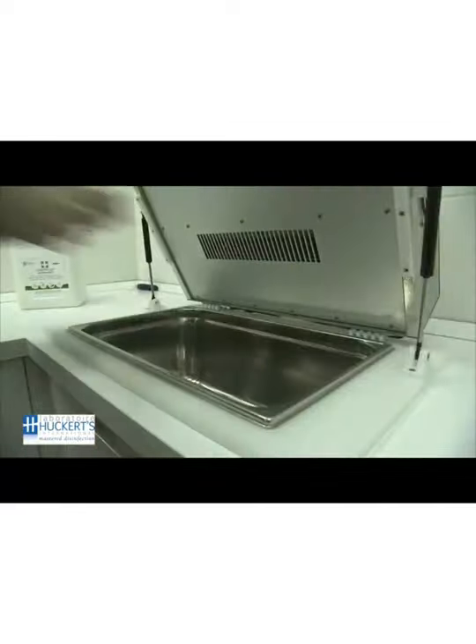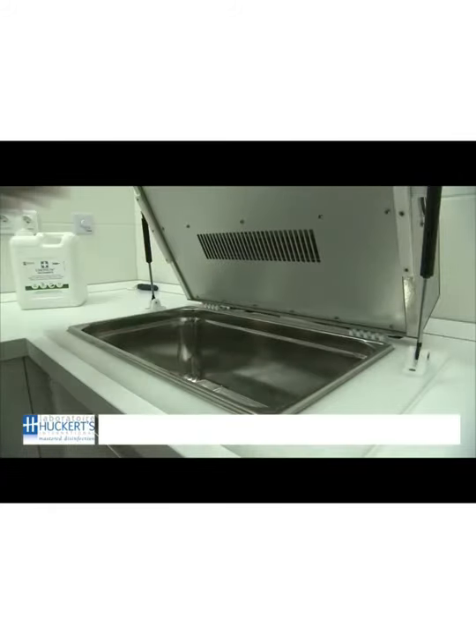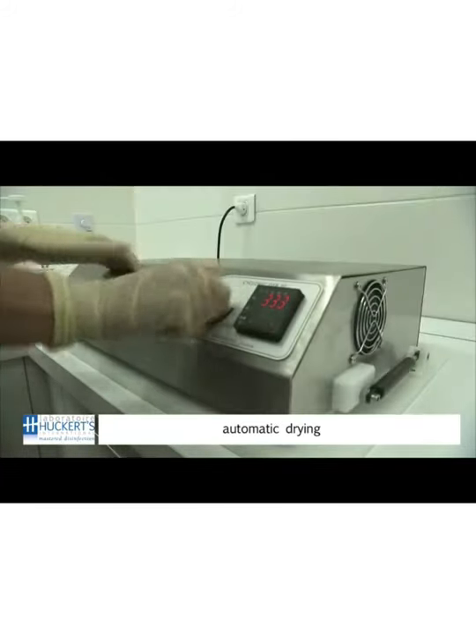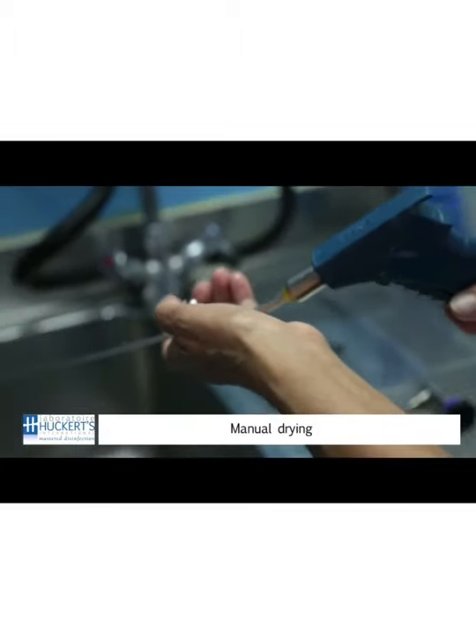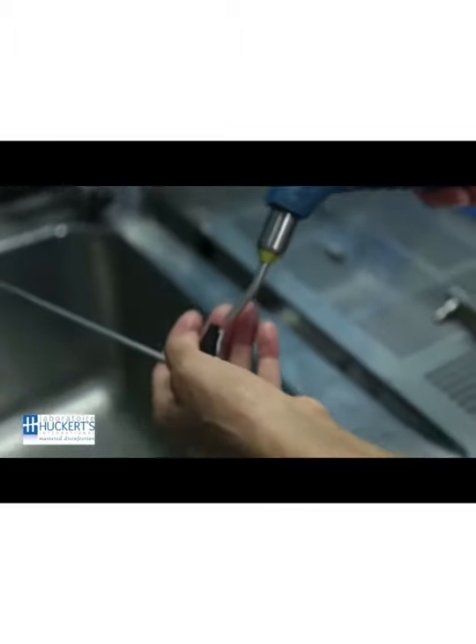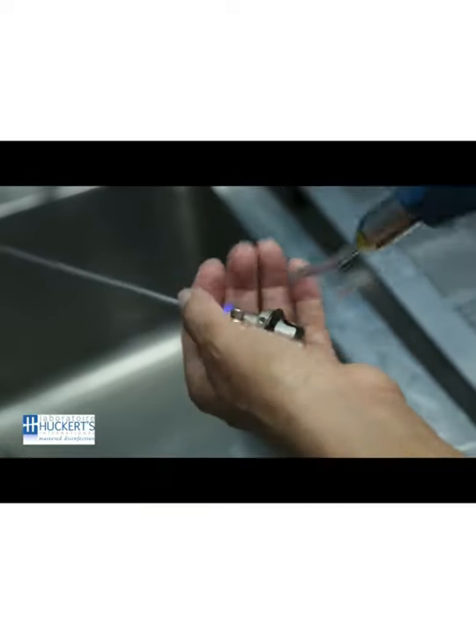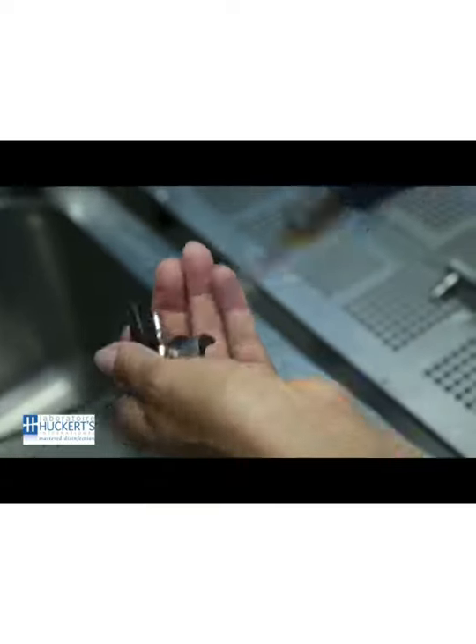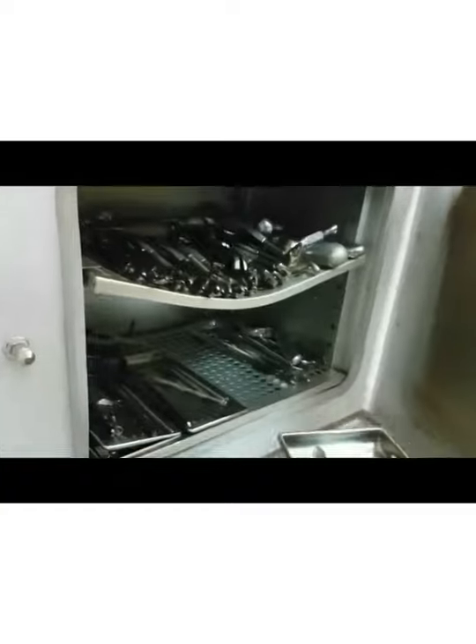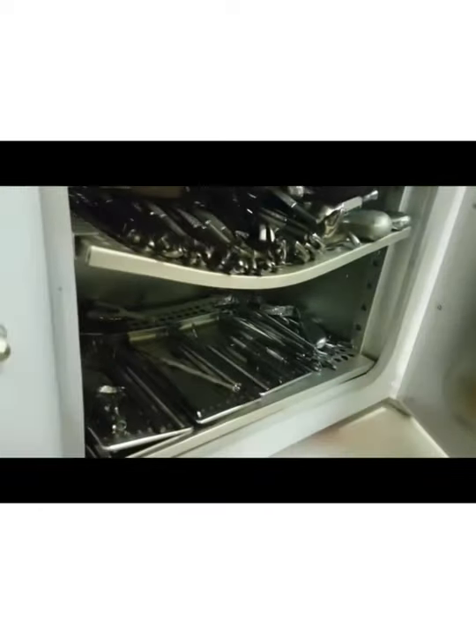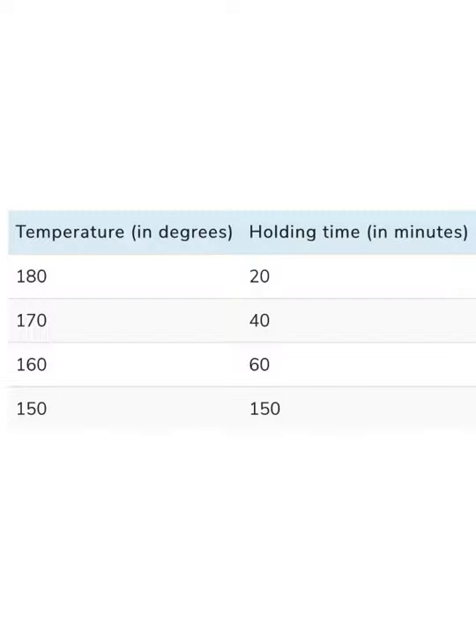It is really important to bear in mind that only dry instruments can be put inside the oven for maximum sterilization effect and to prevent the machine from breaking. And then we transfer clean and dried instruments into the oven. The table shows the recommended time and temperature for maximal sterilization effect.